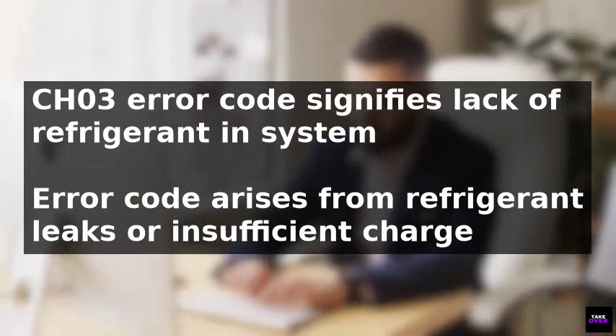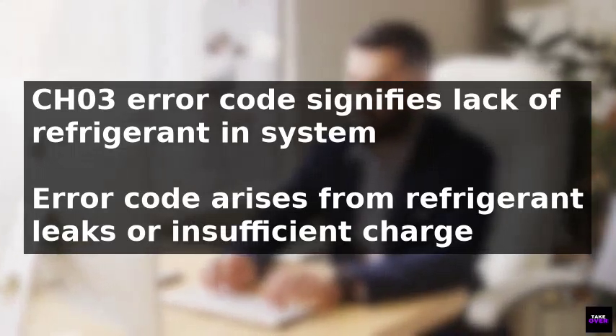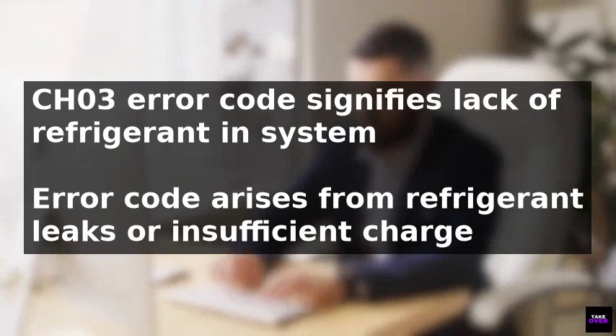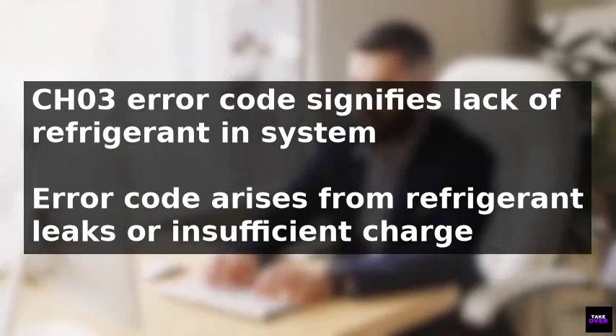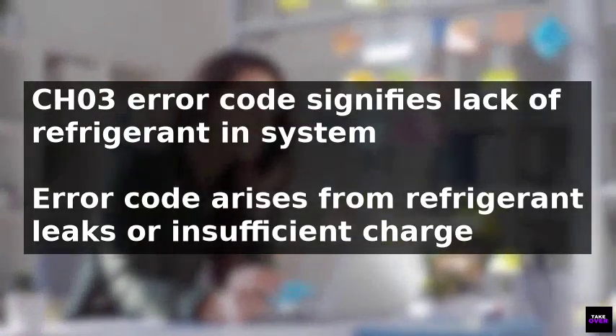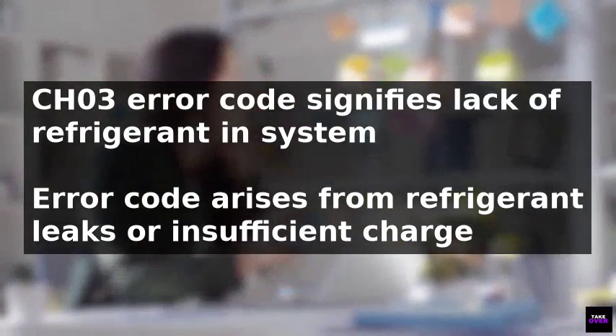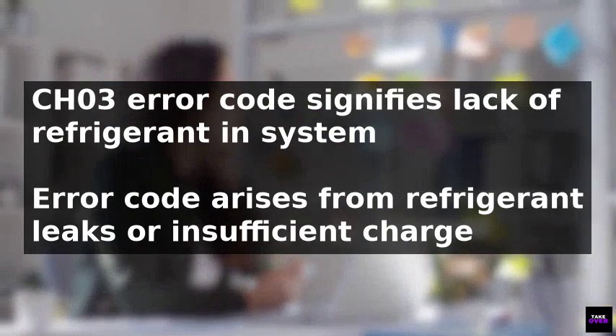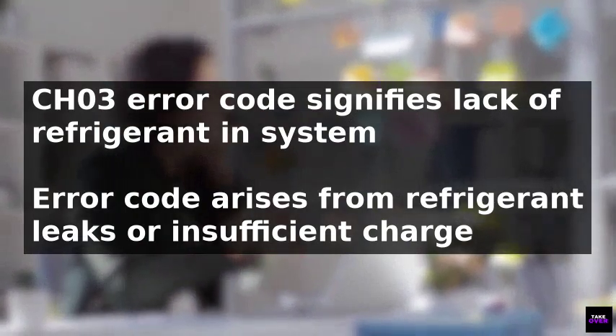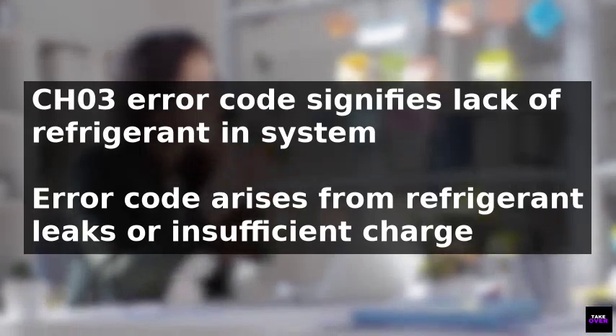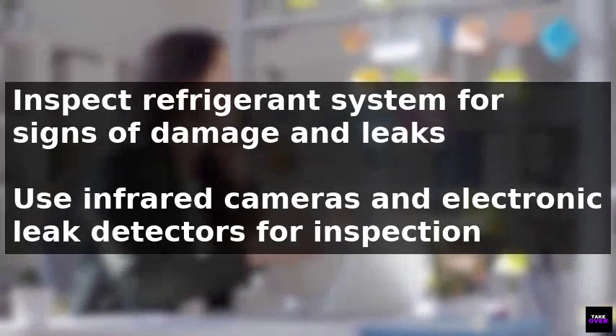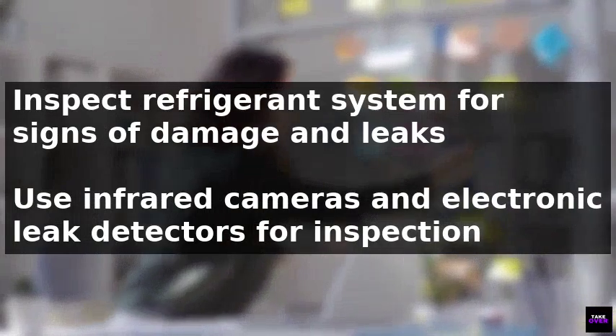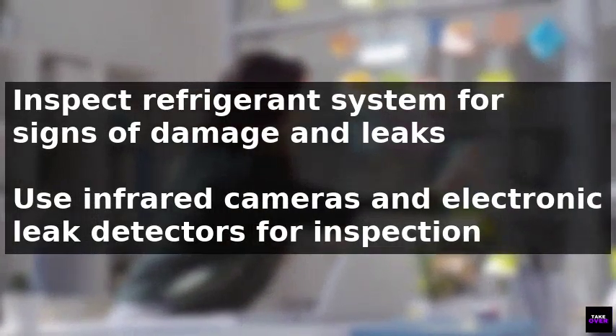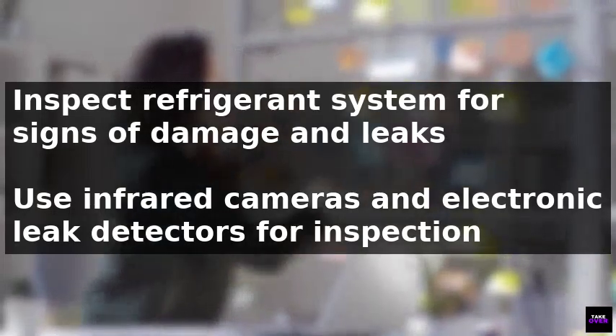To fix the CH03 error code on an LG air conditioner, it's essential to understand what this code signifies. The CH03 error code indicates that the system has detected a lack of refrigerant. This issue can arise due to several causes, including a refrigerant leak caused by damaged ports or improper installation, as well as an insufficient refrigerant charge.